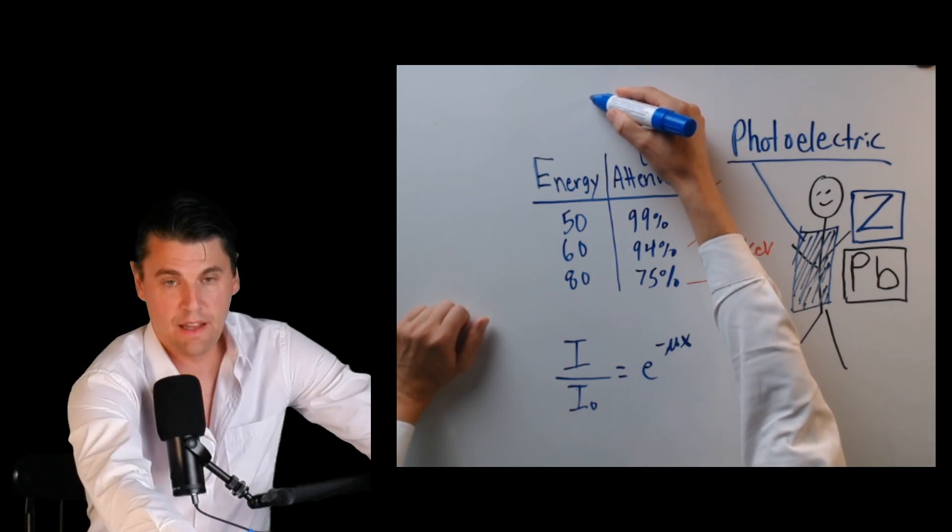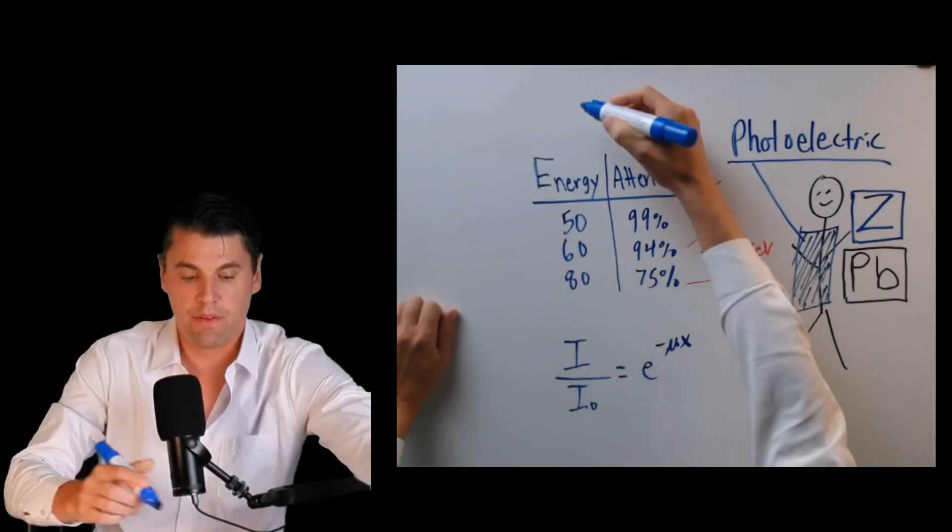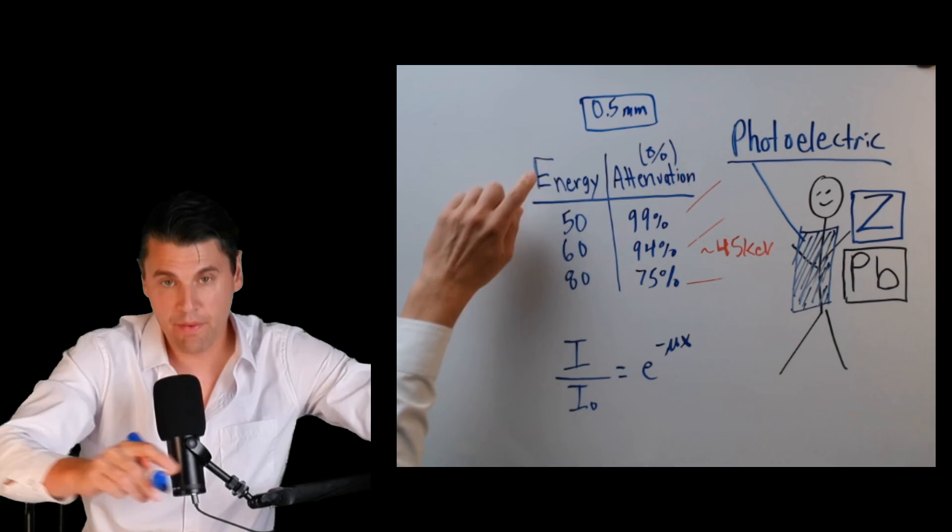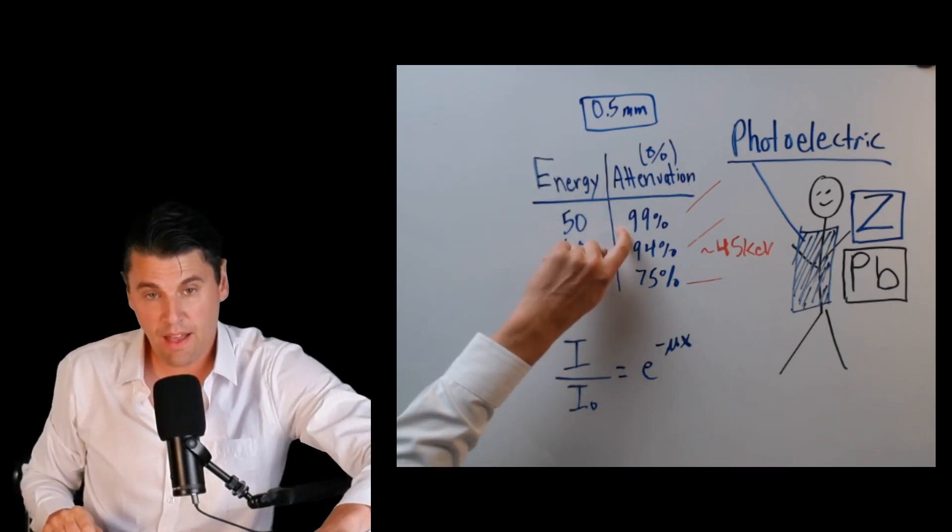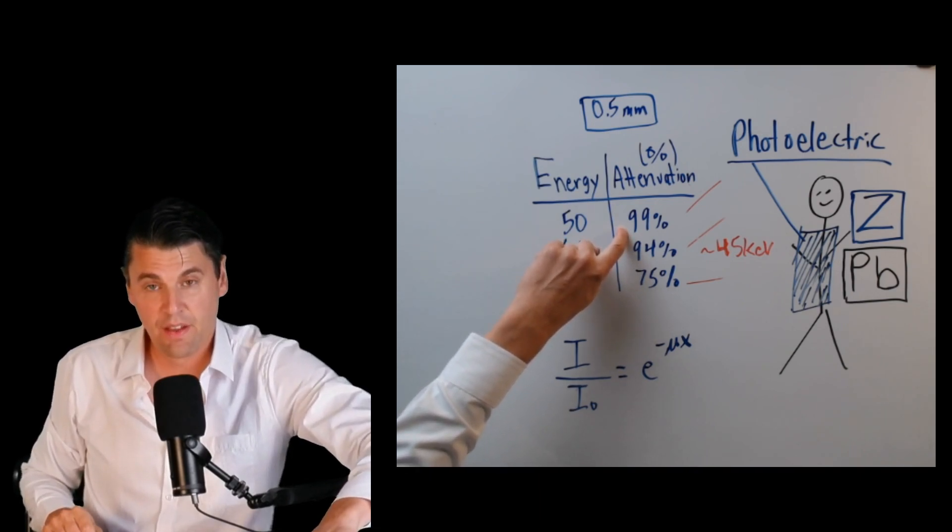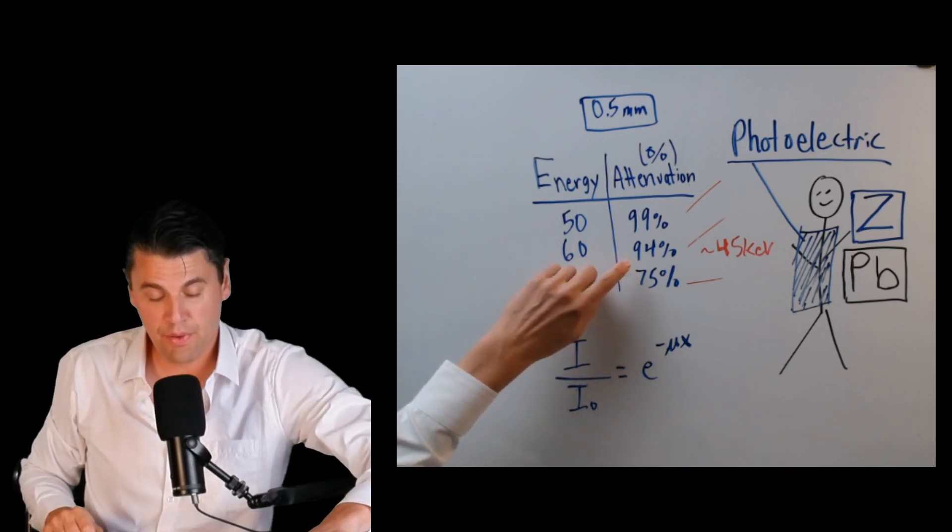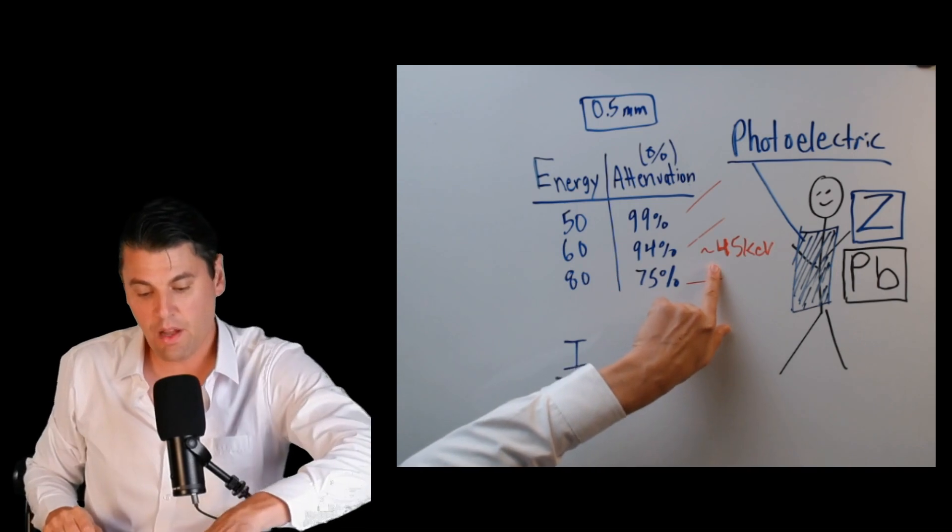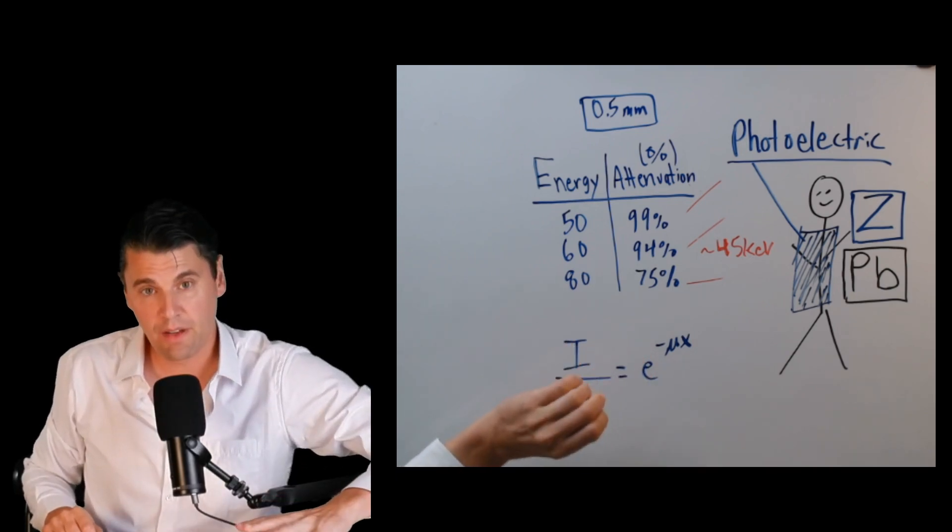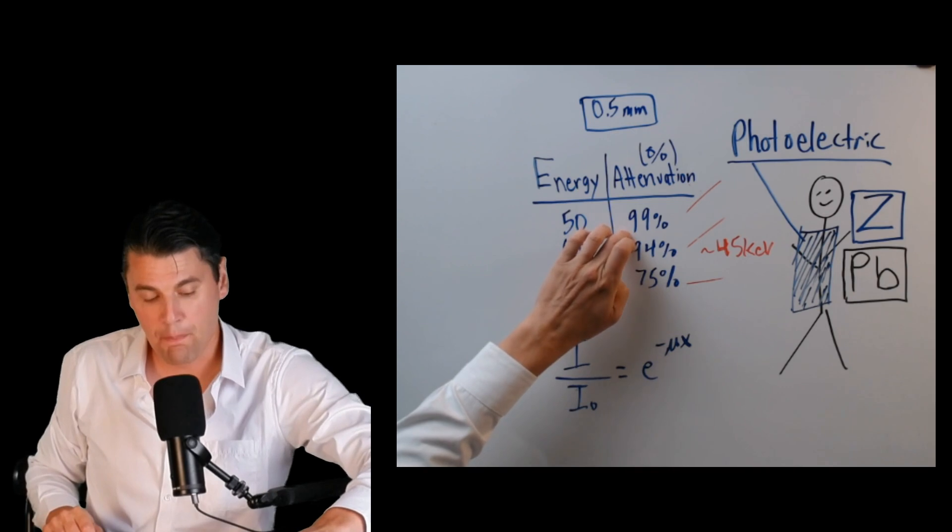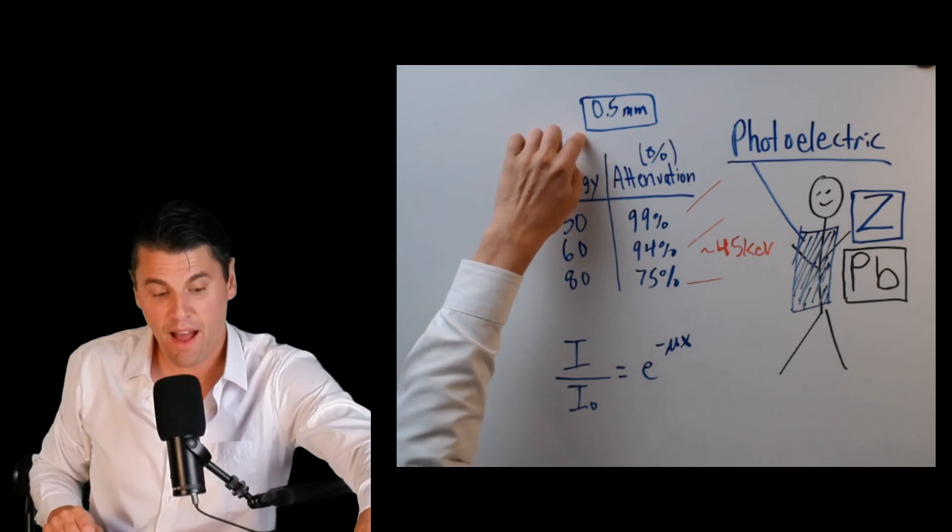This table here is actually for 0.5 millimeters of lead. If you have 0.5 millimeters of lead and the energy of 50 KEV, you're going to stop 99% of the x-rays. The energy is 60 KEV, 94%, and so on. And like we talked about, those scattered x-rays have a lower energy than the primary x-rays that were coming in. We're going to be stopping actually more than 99% of the x-rays if we have 0.5 millimeters of lead.